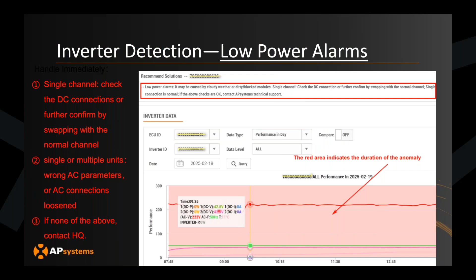One other note also is that sometimes when you disconnect these modules, the voltage jumps back up to the normal voltage, like 35 or 40 or something along those lines. But then when you reconnect them to the microinverter, it drops to 2/3 again. This phenomenon happens because if the diode goes bad, you only see the problem when the module is under load, or when you're trying to produce power from it. So in any case, that's something that we've noticed in the field, where the voltage drops by a third. That usually indicates a diode problem on the module. It's very rare, but it happens sometimes. So that's a side note that we've sometimes seen in the field.